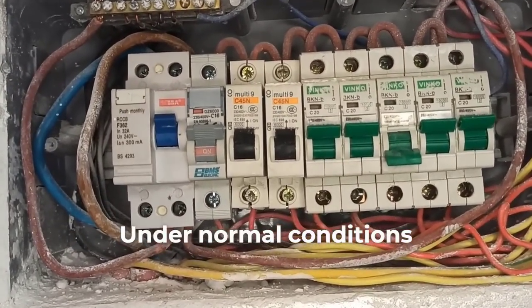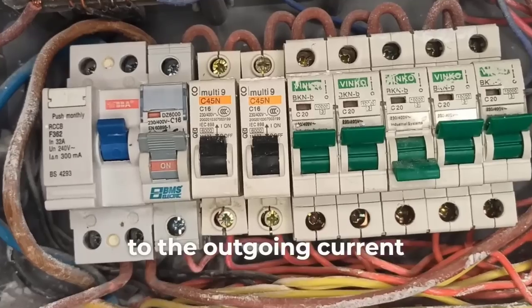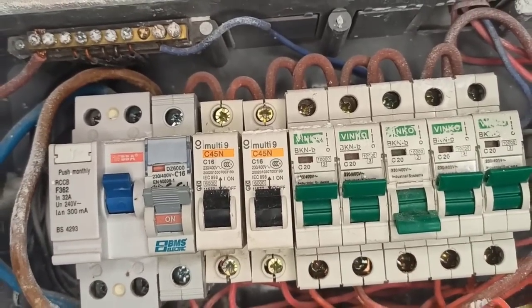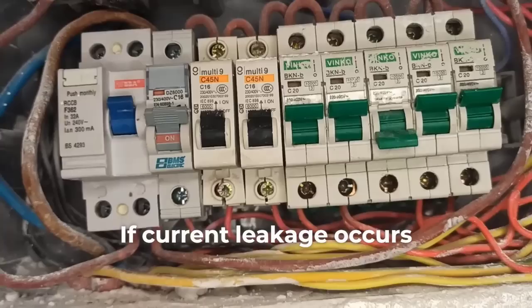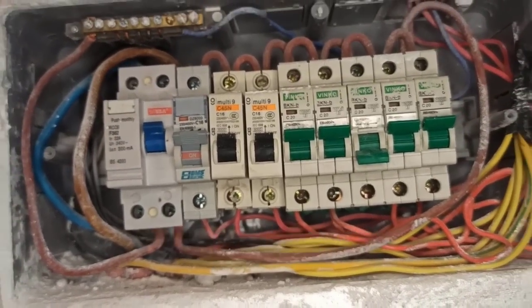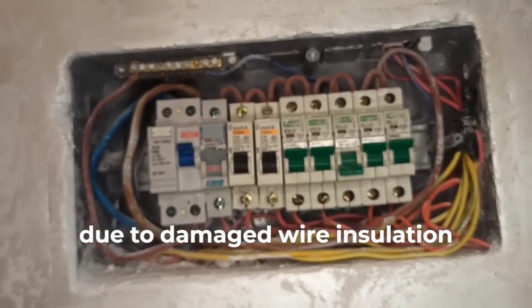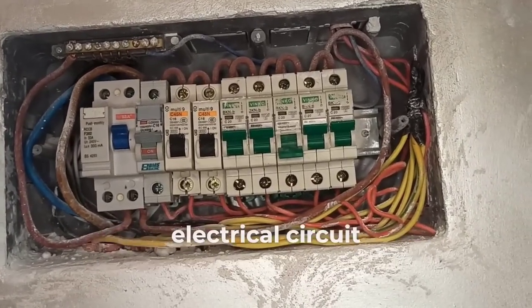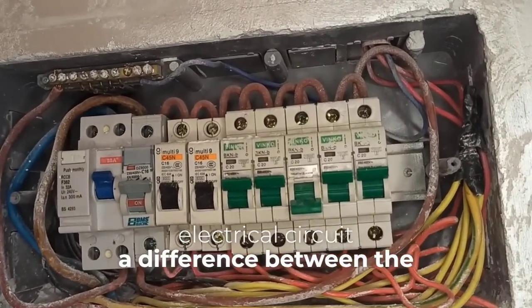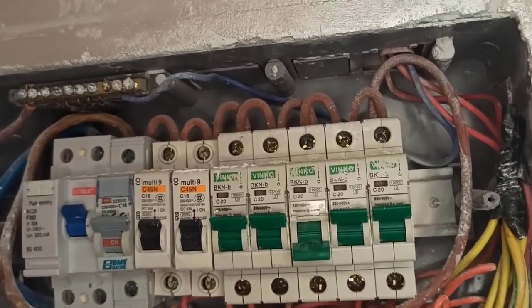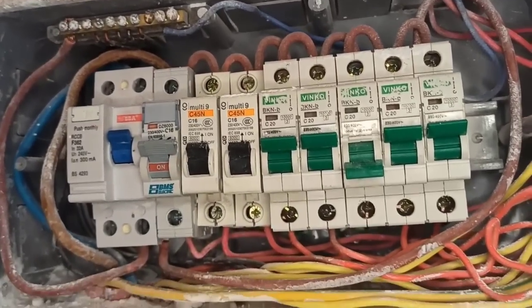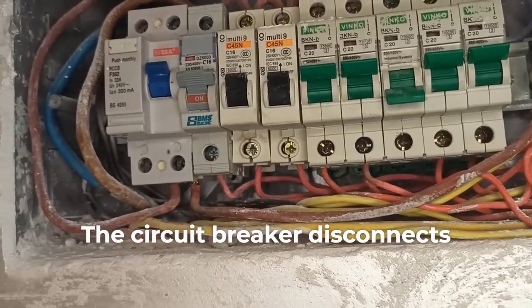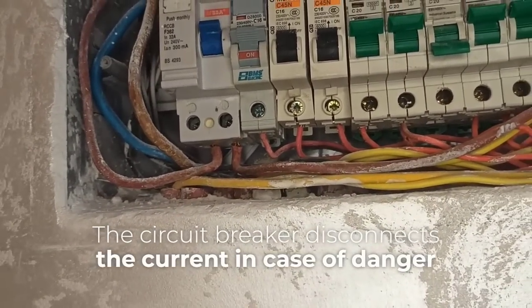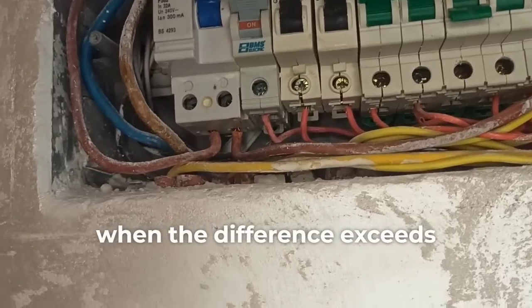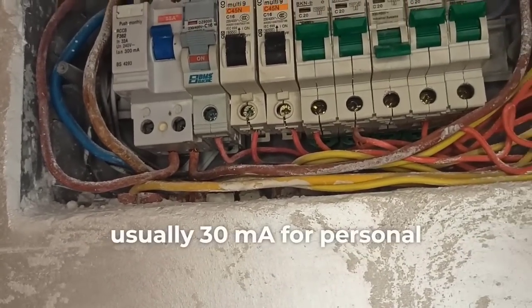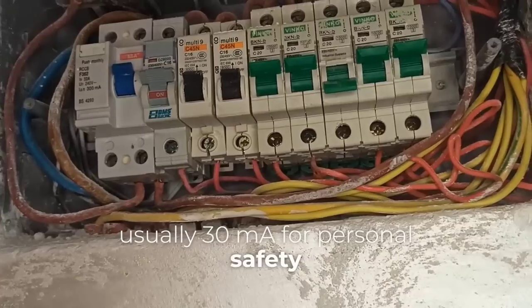Under normal conditions, the incoming current is equal to the outgoing current. If current leakage occurs, for example, due to damaged wire insulation or human contact with the electrical circuit, a difference between the two currents appears. The circuit breaker disconnects the current in case of danger when the difference exceeds a specific value, usually 30 mA for personal safety.